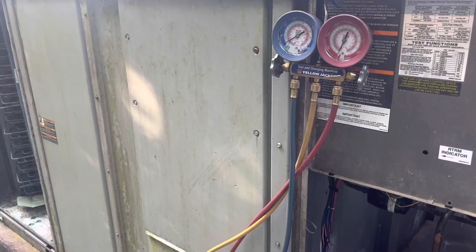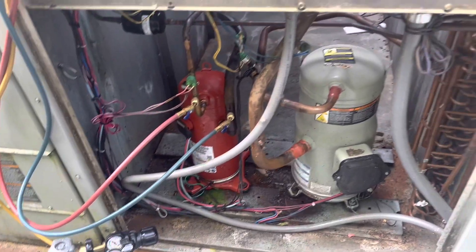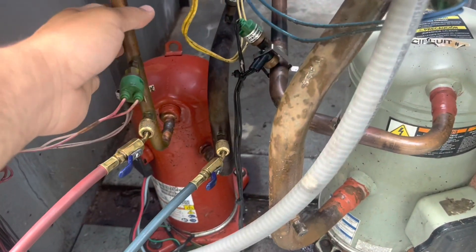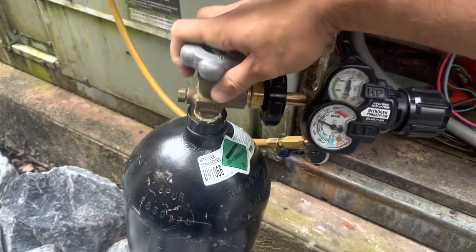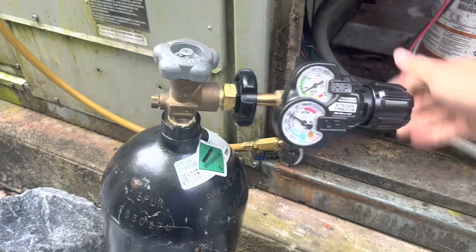All right guys, got a 15-ton Trane unit that has a leak — going to do a nitrogen test. Circuit one, they said the leak is in circuit two, so we connect our gauges to the liquid side and the vapor side. Nitrogen's connected, so we're going to see if we can find the leak by using the nitrogen — so open this up.